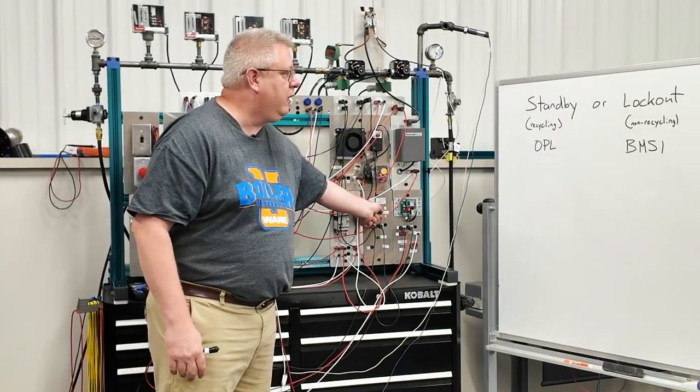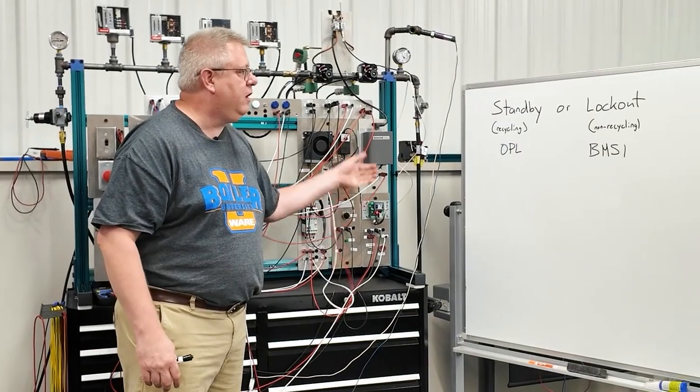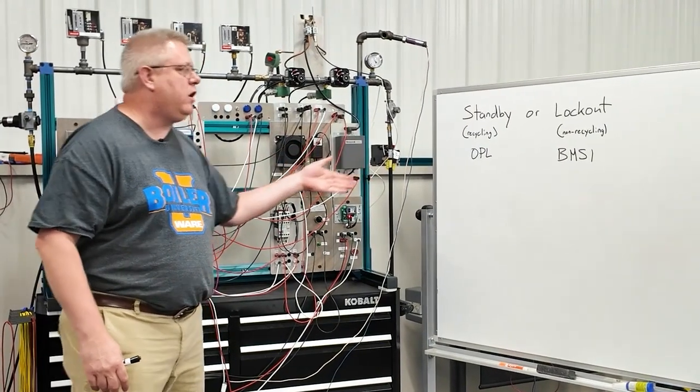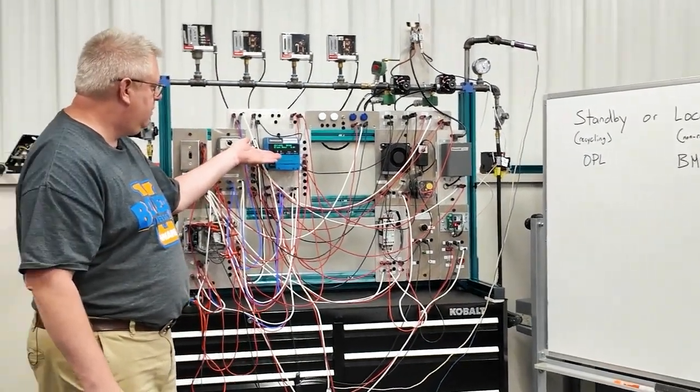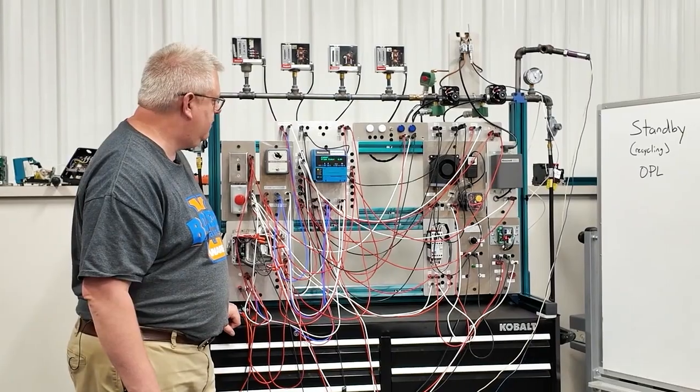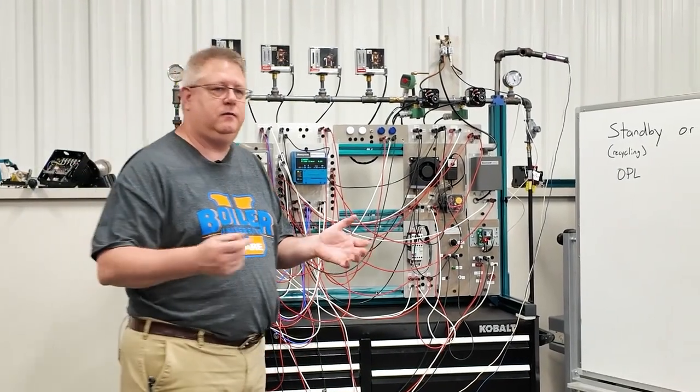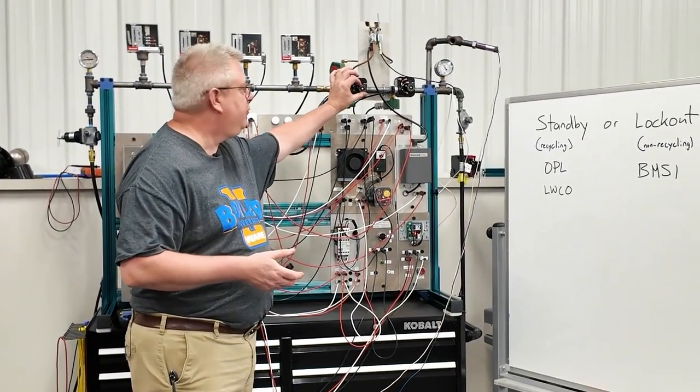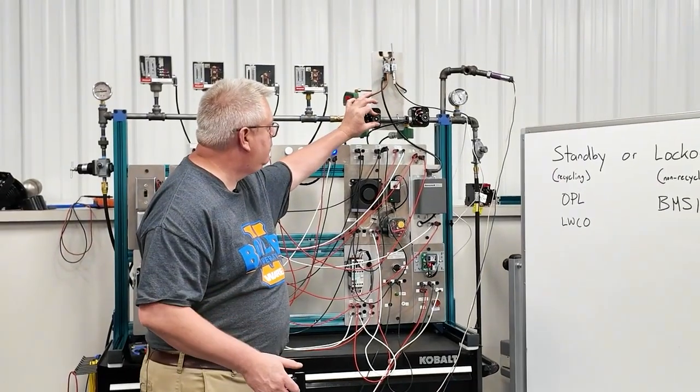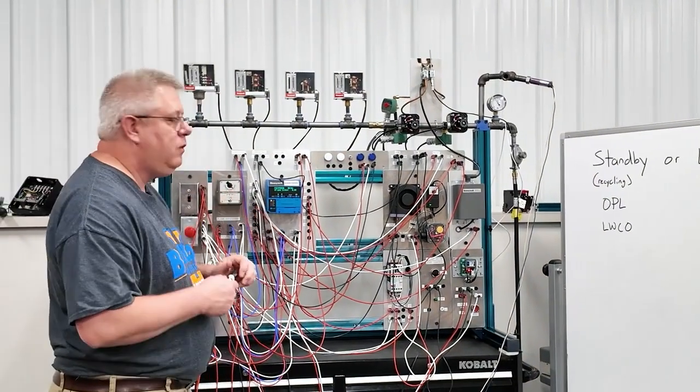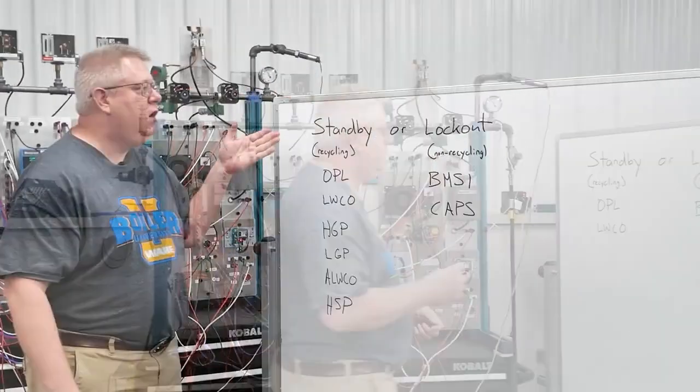If we blow down the boiler and trip it on the primary low water cutoff, we're back to standby. Now I'm going to trip the high gas pressure switch. We've gone into standby again.